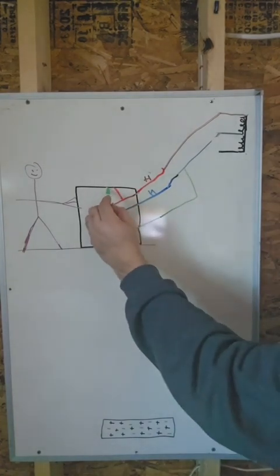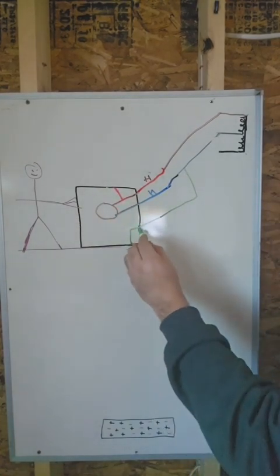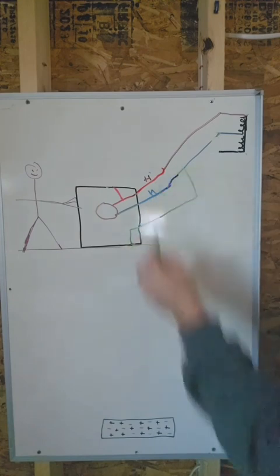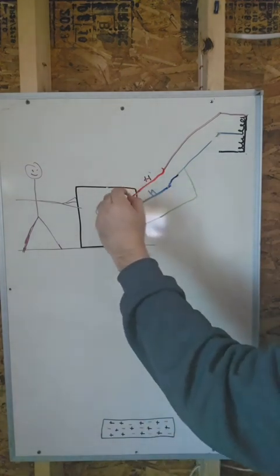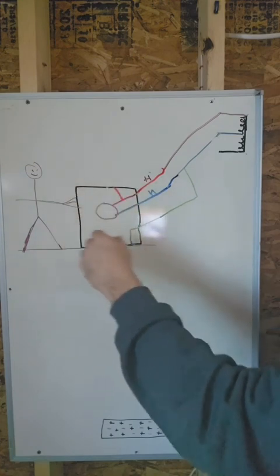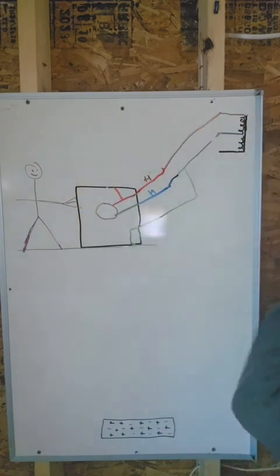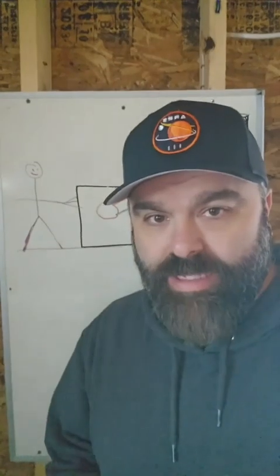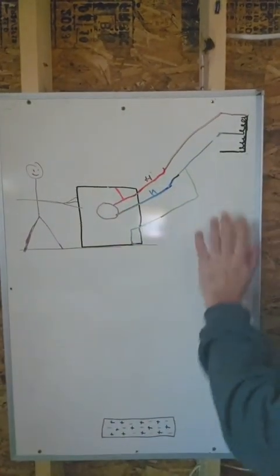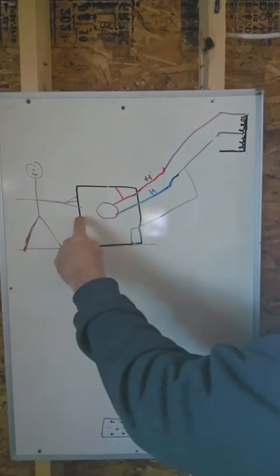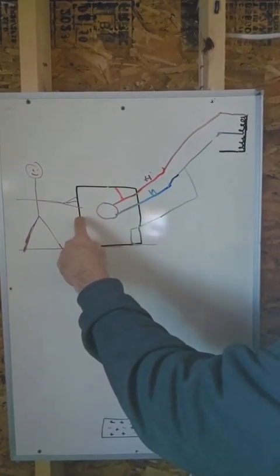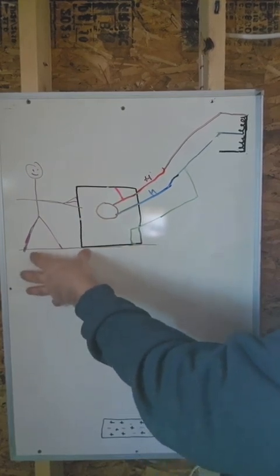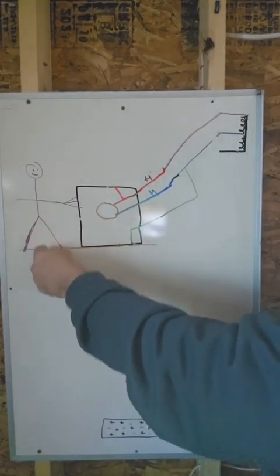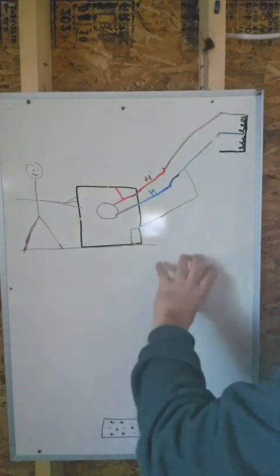So now when this becomes live, this casing becomes energized, this wire will become energized, and now the hot wire ahead of the motor, if there was a nick, connects to the neutral through the ground, totally overloading it and tripping the breaker. Now the next thing we do: if something was to go wrong on a different circuit and energize the dirt, this is grounded, which is essentially 0 volts, and the dirt and the earth could become energized, and the electricity now is a shock hazard that way.